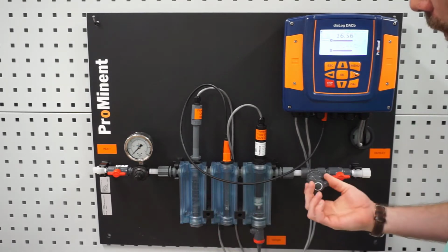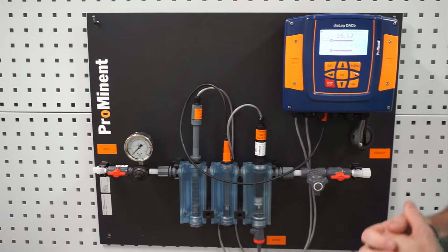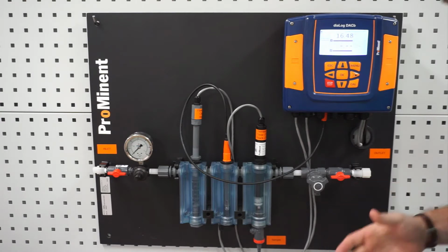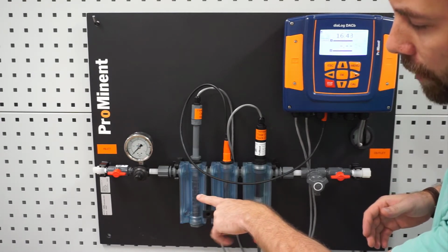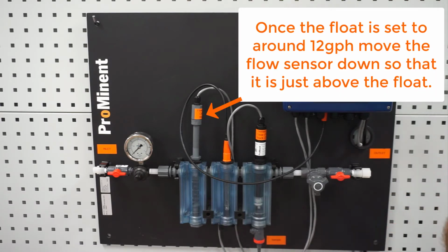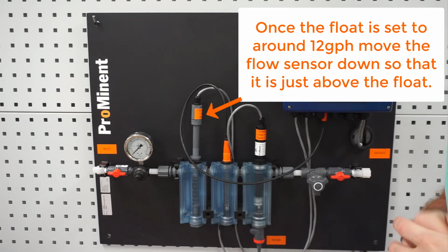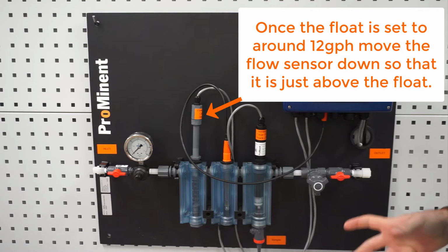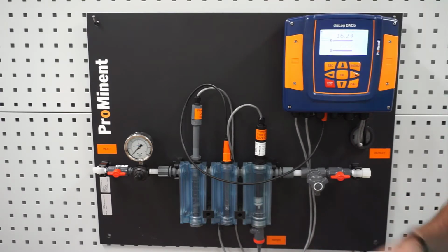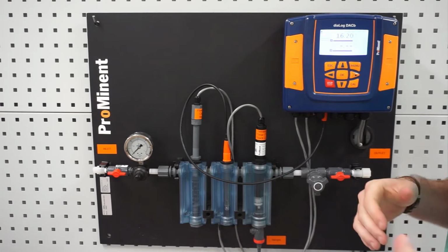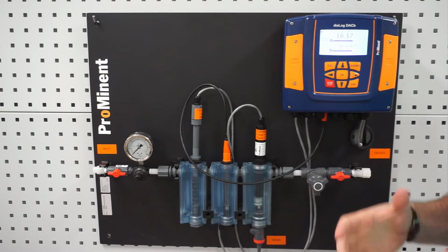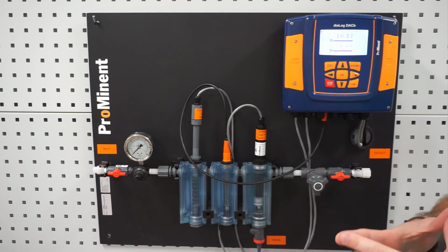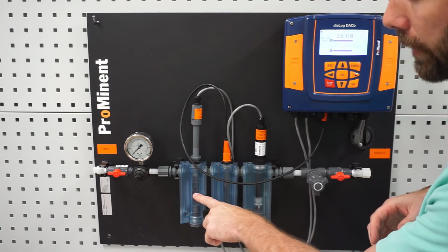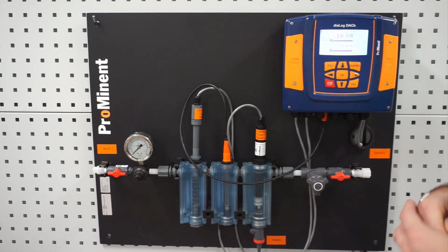Next step would be adjusting our flow, and we're going to adjust that with our needle valve here. Ideally, we found that a good starting point is right around, there's a dash mark on here, right around 12 gallons an hour. That is typically a good starting point. The more flow you have going past our amperometric sensor, that will keep the cap cleaner, but it may also draw out that electrolyte faster. So you may have to replace the electrolyte sooner. The slower the flow is going through there, the longer the electrolyte's going to last in the cap, but your membrane may get fouled up depending on what's in the water. So a good starting point is around this 12 mark, and then you can play with that depending on what's in your water and depending on the actual application. You can either increase that or decrease that flow.